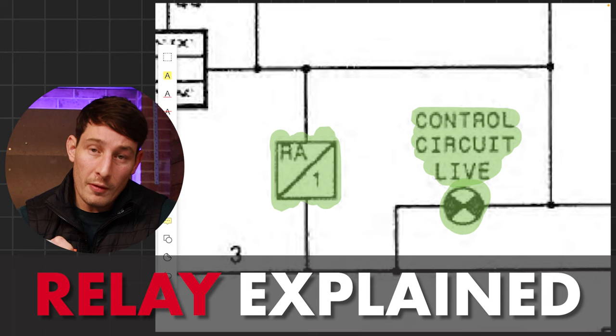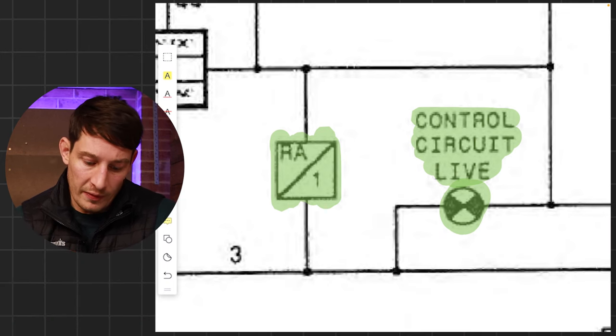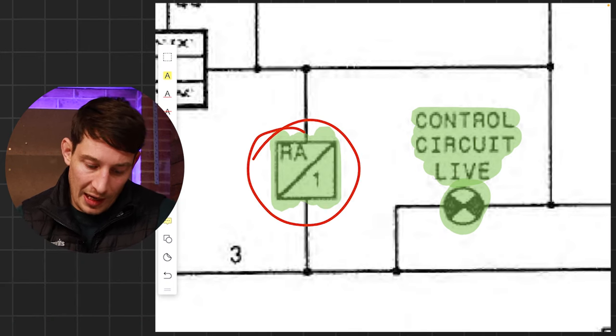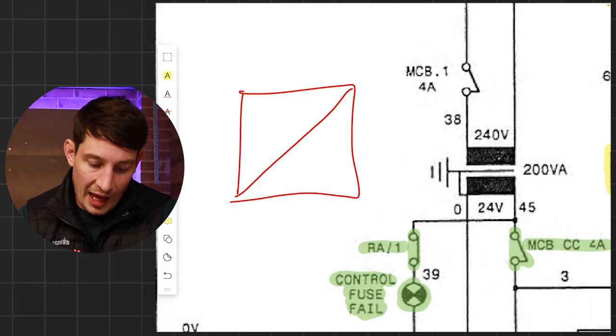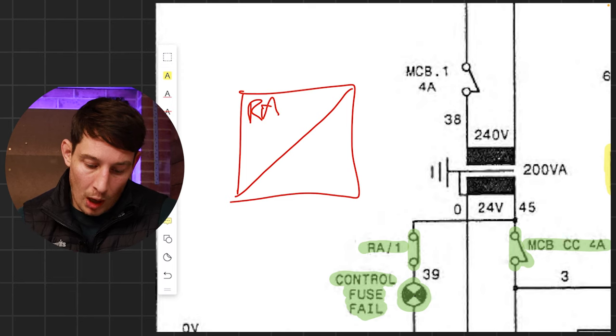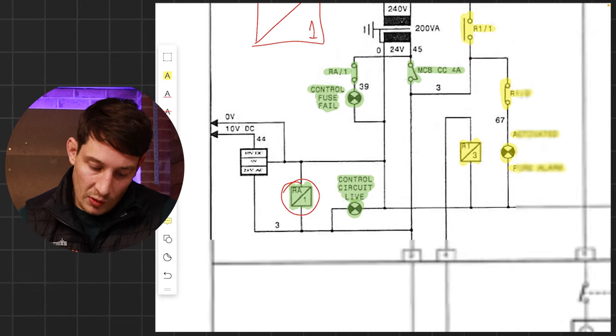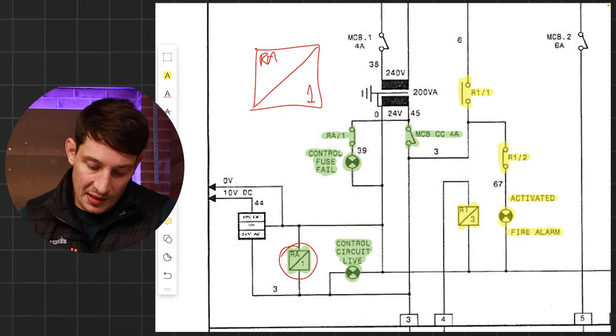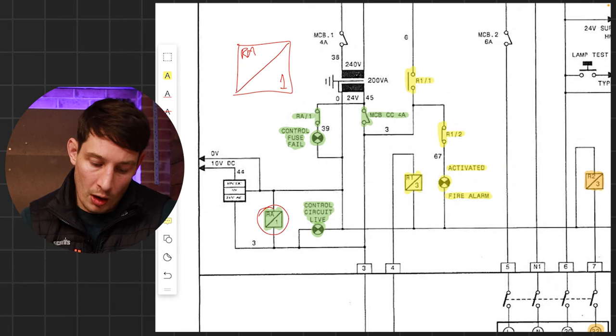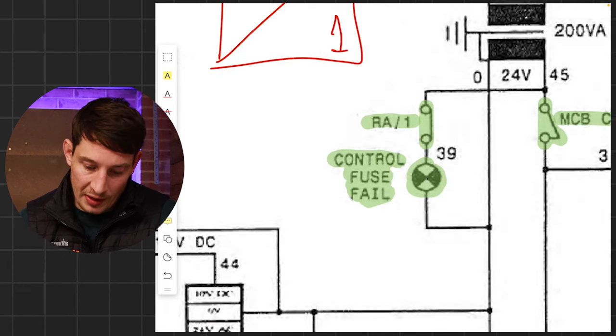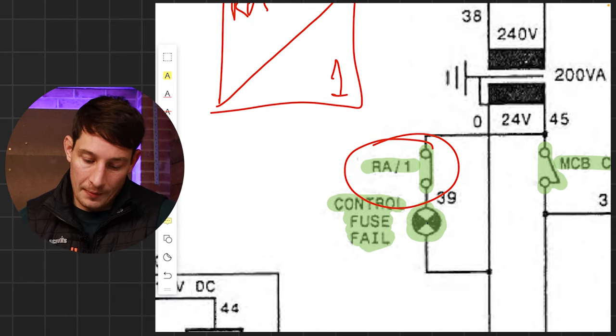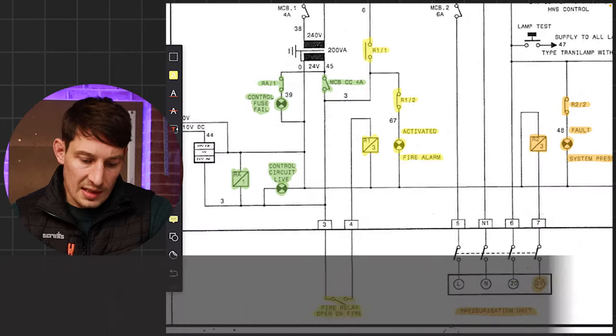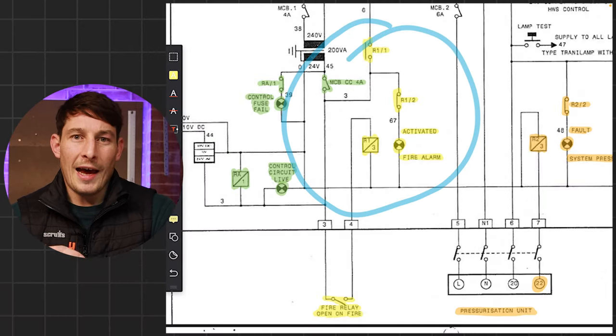Quick explanation of the relays we see in this schematic. Take relay RA1 — the box gives us the name 'RA', and the number '1' tells us how many poles are associated with it. So straight away we know there's one thing being controlled when this energizes. Over here is the normally closed contact of RA, and it tells us this is pole one. Now let's have a look at the yellow subsection.